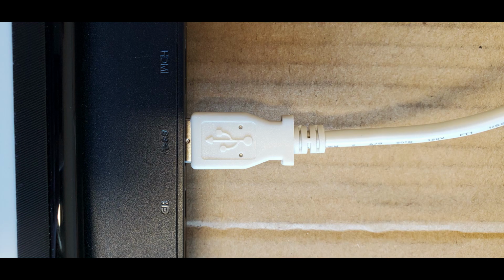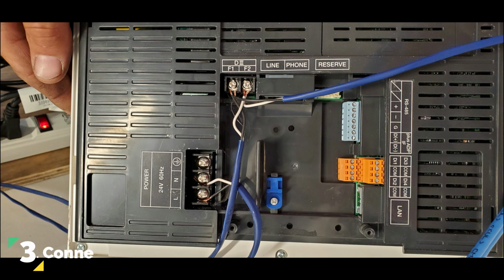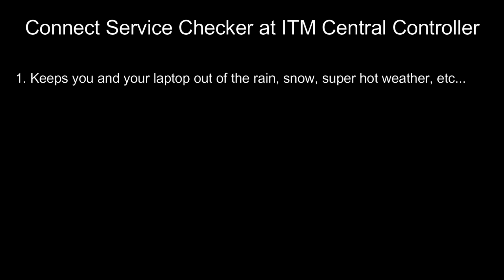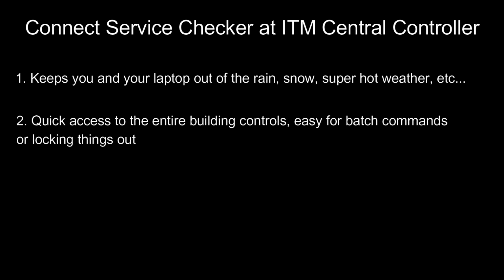Before we start recording any data, we need to make sure the service checker is connected properly. You want to connect the service checker to one end of the outdoor unit F1, F2 daisy chain. This ensures you will see everything installed on site. I will commonly connect to the end of the comm wire landed at the ITM central controller, and I do this for a few reasons. Reason number one is in my area of North America, it rains a lot. So connecting to the ITM means I'm connecting inside the building, staying dry and out of the elements. The other reason I like to connect here is for quick, easy access to the entire building controls via the ITM.